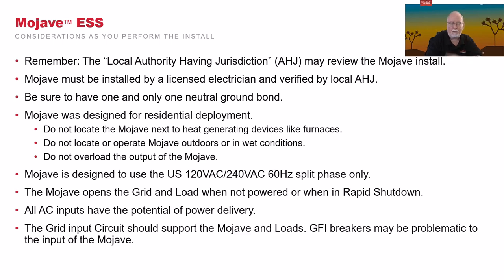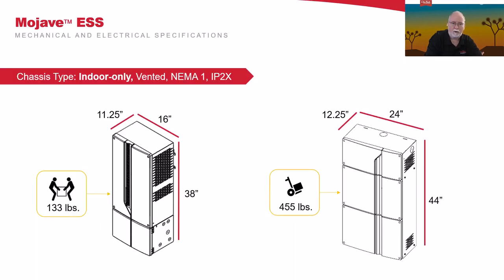Another aspect of this is that you have to remember that every input actually has the ability to have AC on it. So the grid has AC on it, the generator could have AC on it, even the grid direct PV, if things go wrong. Whatever, you want to make sure that you're always doing the proper lockout tagout procedures. The grid input circuit should support both the loads and what Mojave needs for charging, so size that accordingly.